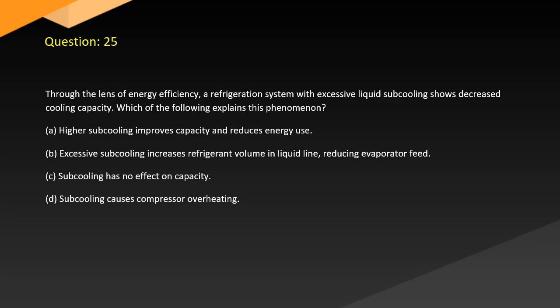Question 25. Through the lens of energy efficiency, a refrigeration system with excessive liquid subcooling shows decreased cooling capacity. Which of the following explains this phenomenon? A. Higher subcooling improves capacity and reduces energy use. B. Excessive subcooling increases refrigerant volume in liquid line, reducing evaporator feed. C. Subcooling has no effect on capacity. D. Subcooling causes compressor overheating.